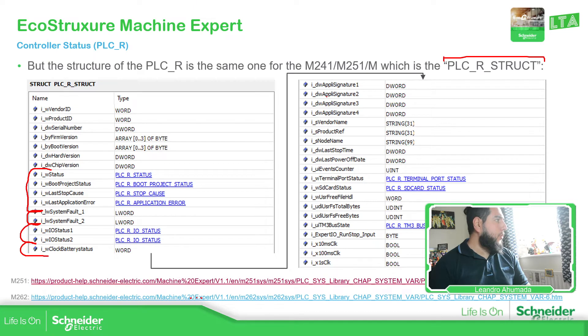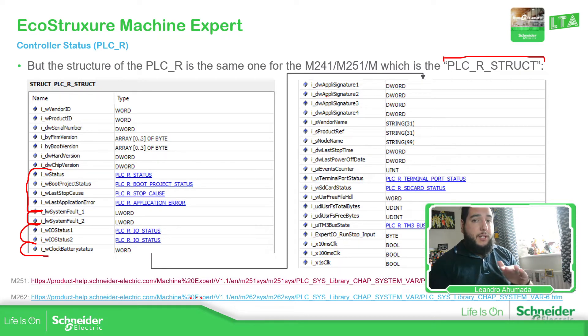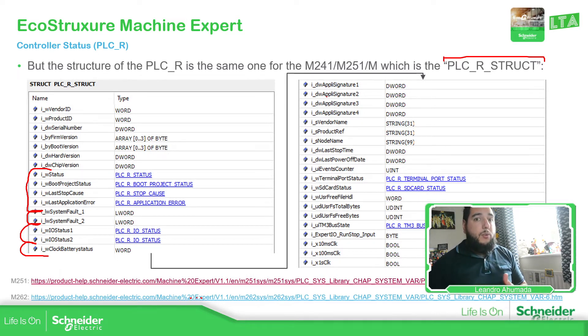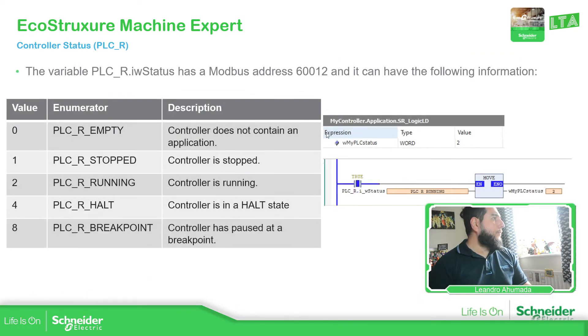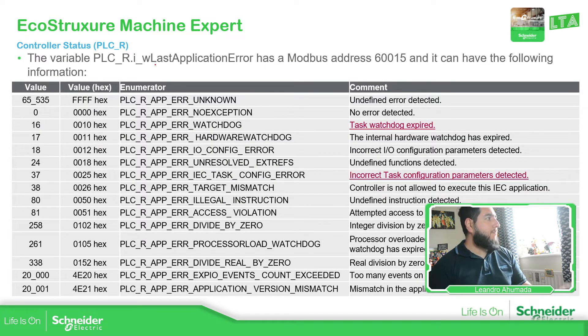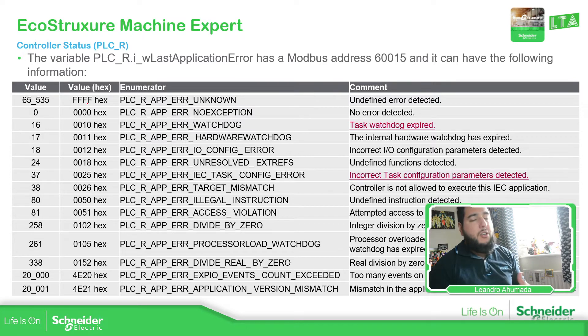What you need to know is you have the PLC underscore GVL that has a huge structure, and inside that PLC underscore GVL you have this PLC underscore R that allows you to see in detail the actual structure of the controller. However, this information can also be accessed via the web server of the PLC. If it's already enabled, you just need to go to the diagnostic and you can see most of the same information in a different way. You also have the last application error — it's the same as I showed you in the manual. What you need to check is the value, and then if you want you can add it in an HMI or a converter if you're using Machine Expert.